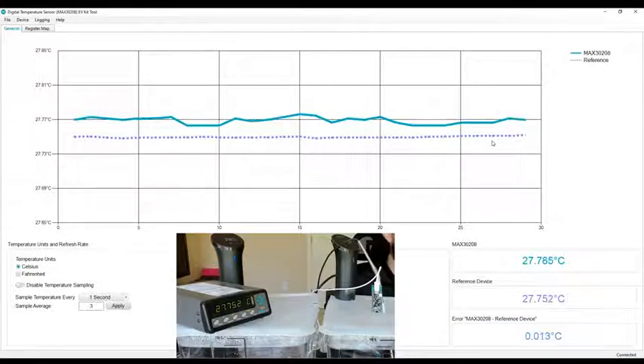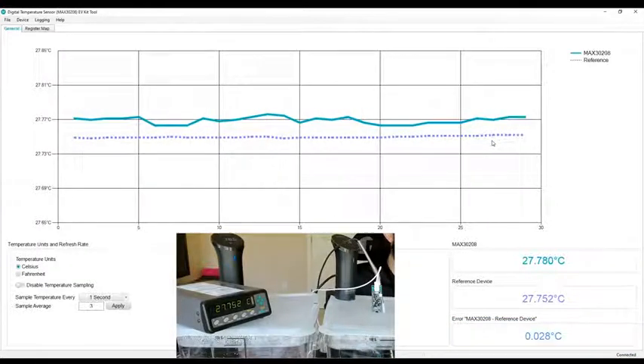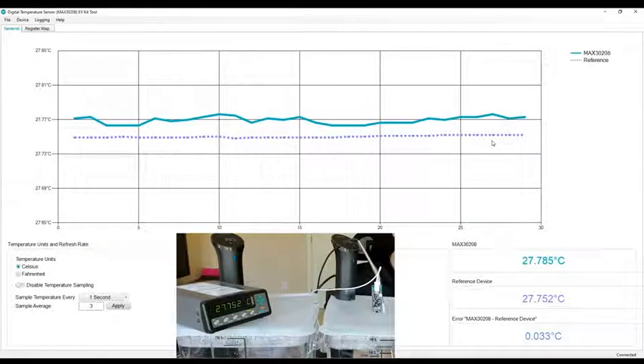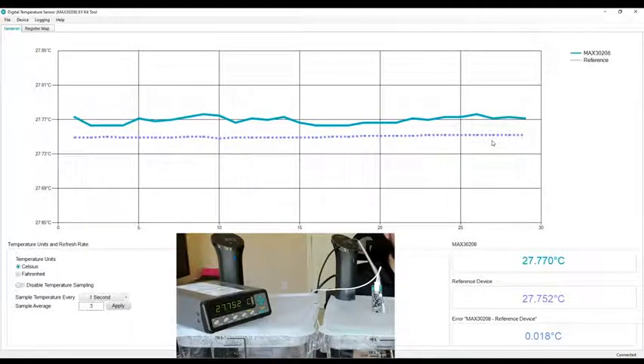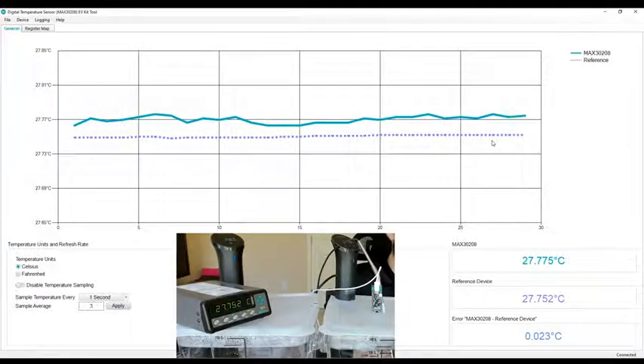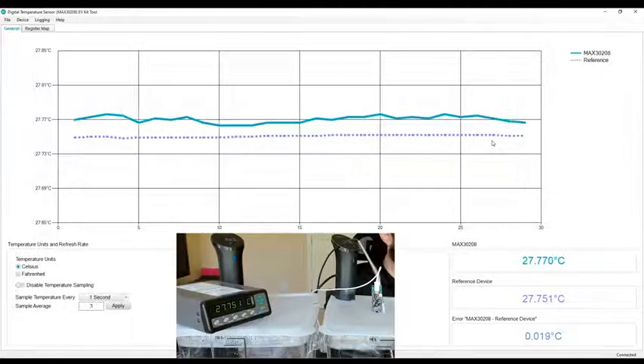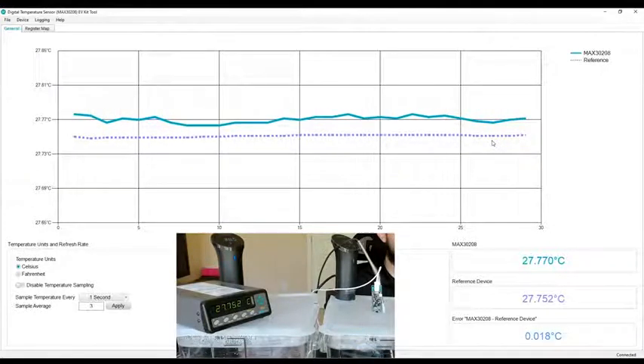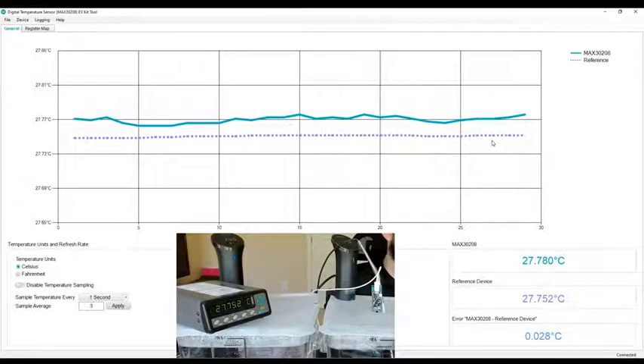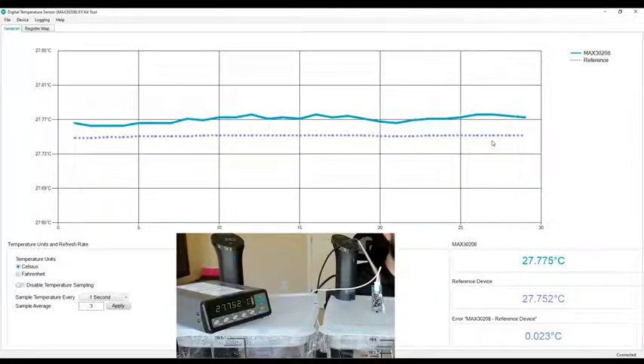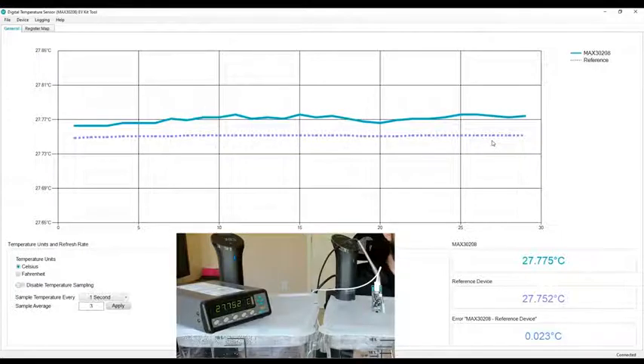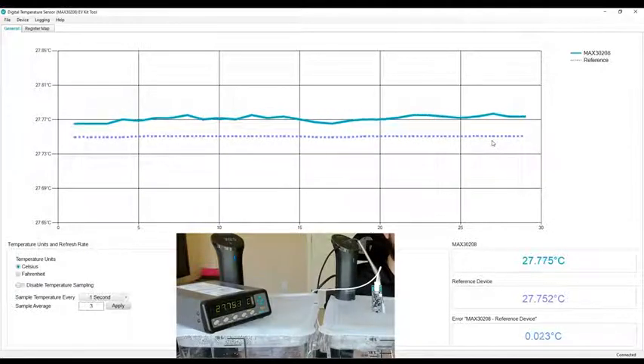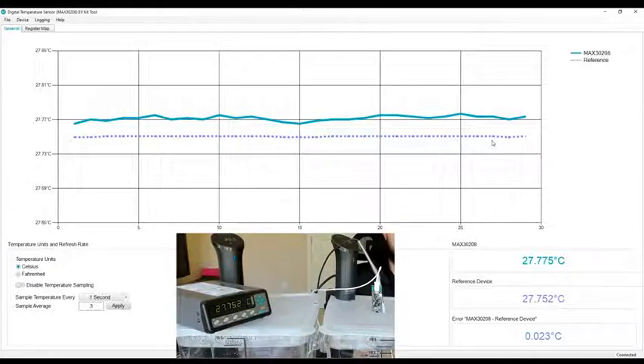We're also graphing these just above so you can see the difference visually. It does look like they may be somewhat far apart, but this is due to how we do the scaling on our GUI. We essentially have whatever temperature the reference device is at, and then we have 0.1 degrees Celsius above and below. So keeping that in mind, you can see that we're much closer to the reference device than what our spec truly is.